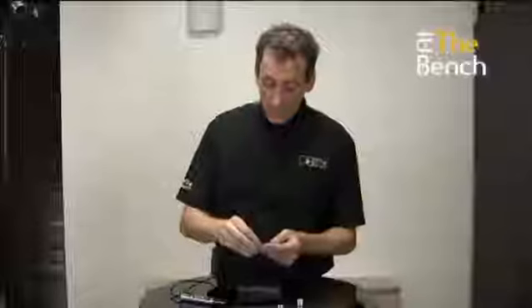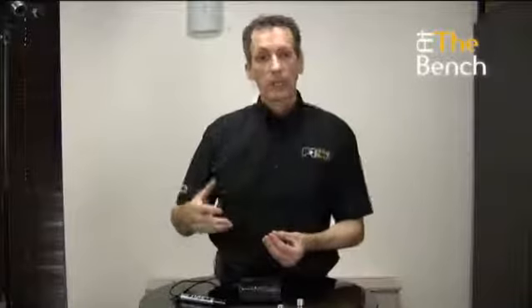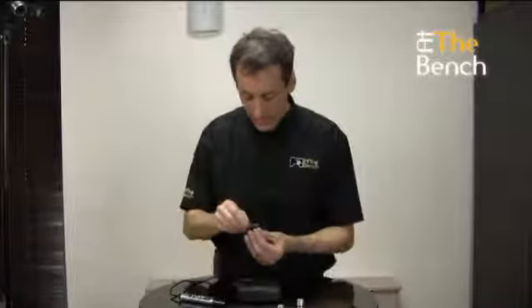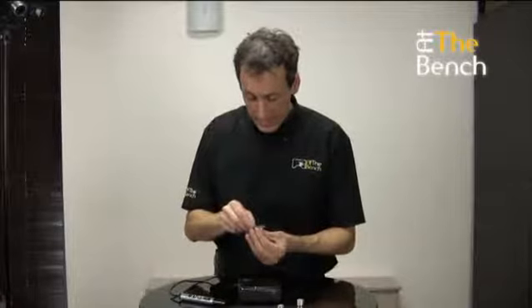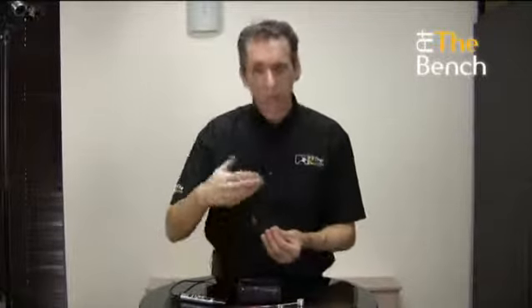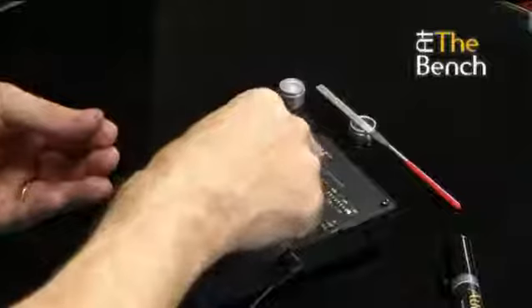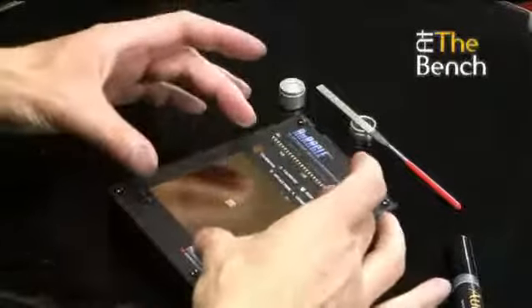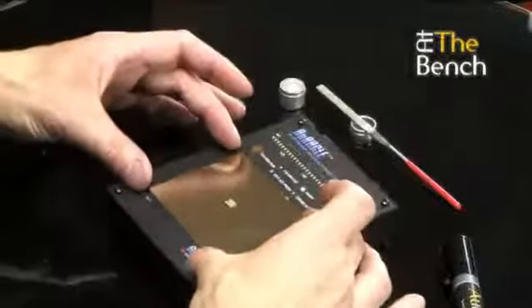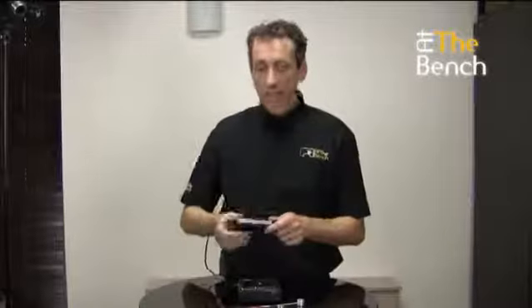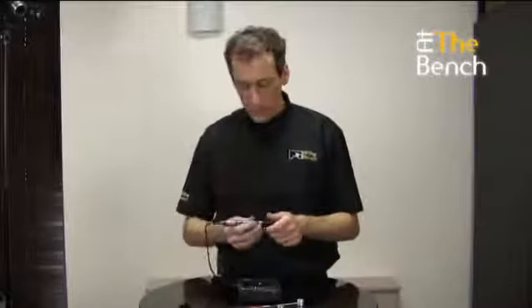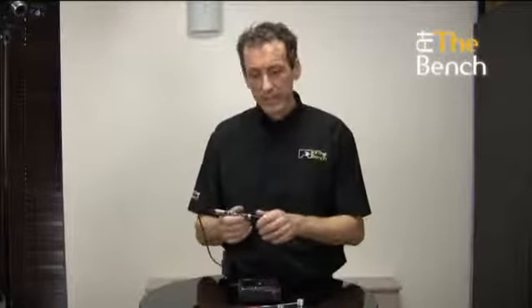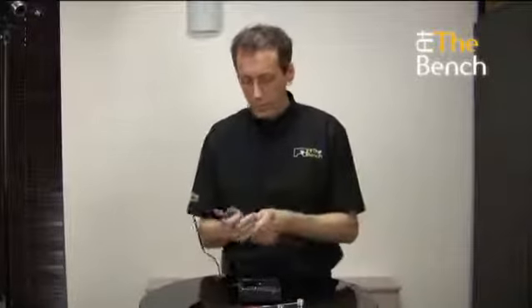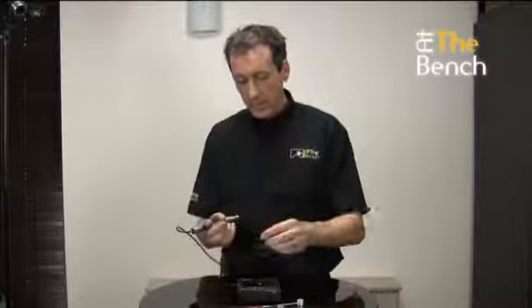So what we need to do is to clean the surface to provide a good electrical contact. The file comes into play, it's very handy for that. We'll just scrape the top of the piece, we'll put it upon the area here. This is a metallic testing plate. The pen is full of a salt solution. Sometimes when you take the lid off, you may find a couple of drops will come out. The tip, just wipe that up with a nice simple tissue.